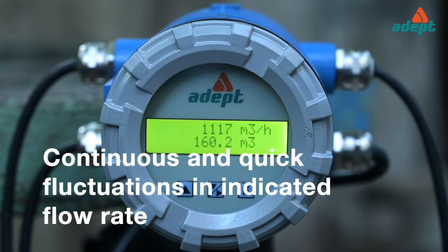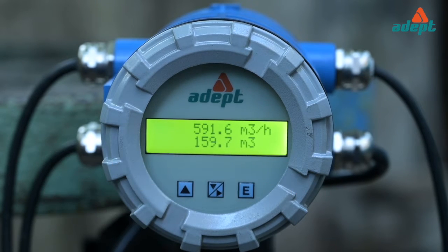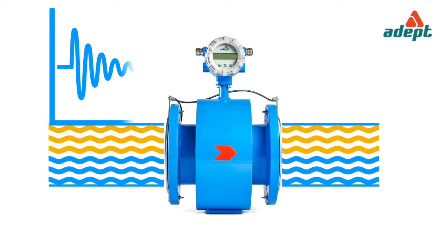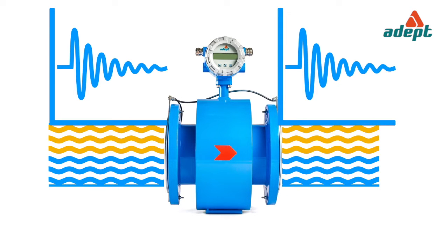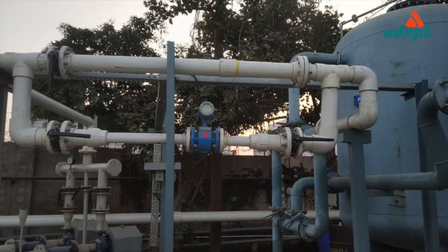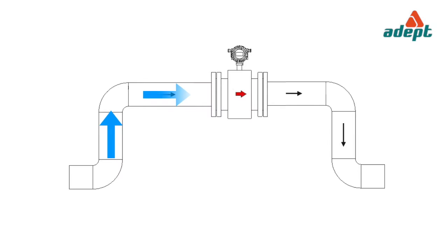Continuous and quick fluctuation in indicated flow rate. Possible causes: damping factor is at a low value; flow is turbulent, pulsating, or changing rapidly; multiple feeder pipes are connected upstream, one of which has pulsating flow; or flow contains bubbles that tend to remain trapped within the flow tube.